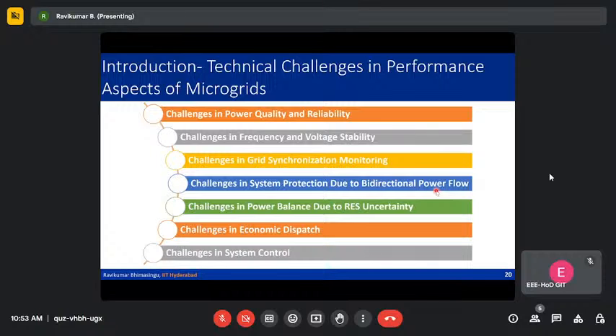There are also challenges in terms of protection due to bidirectional power flow. Generally, in the distribution system where renewable energy sources are not connected, power flow is mostly one directional, like when a fault occurs, power is fed from the substation at the PCC to the fault location. But whenever you have distributed energy sources, the path of the fault changes, and the amount of contribution from both sides changes. You can see there is bidirectional power flow, which creates challenges in system protection.